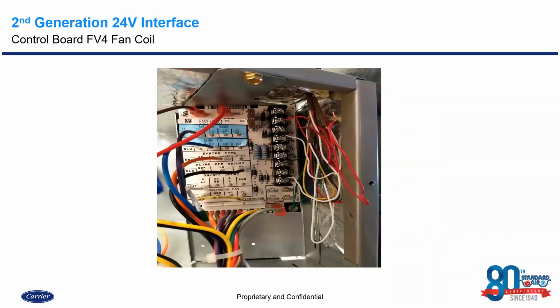And this is what we'll be looking at when we actually open the unit up itself. So we can see on the right hand side, there are taps, depending on what size, what CFM, what system type, what type of auxiliary as far as kW is concerned, and then also our thermostat connections that come from our 24-volt interface on here. Okay, so we'll see we have our R terminal, we have the W2 terminal on here.